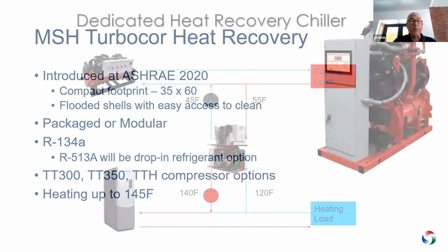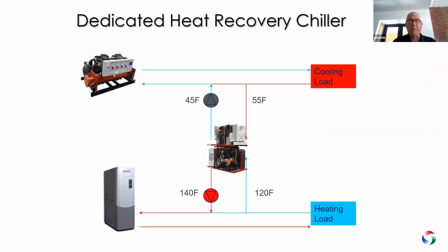You go on to the air-cooled applications. I'm sorry, we'll talk a little bit about what the process is. Typically, you have a cooling load, you have a heating load. The mission here is to try and minimize the footprint of both of those and capture as much of that heat as you possibly can. Your cooling load is doing 55 to 45. We're going to grab some of that heat from that process and put it into the heat side. And conversely, on the heating side, as we work from 120 to 140, we're going to grab some of that heat, some of that cooling, put it back into the other side of the equation.